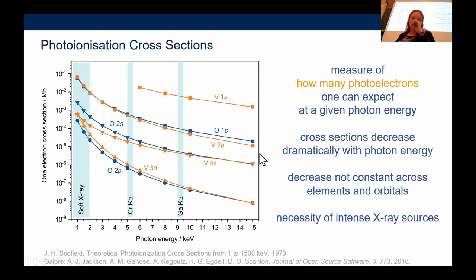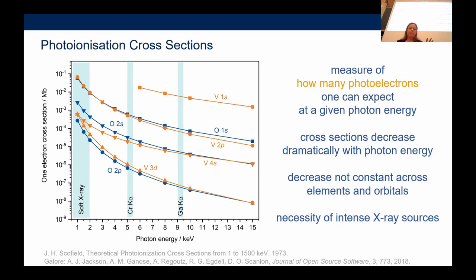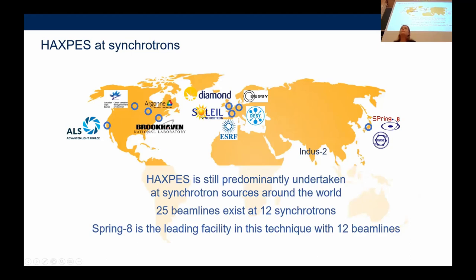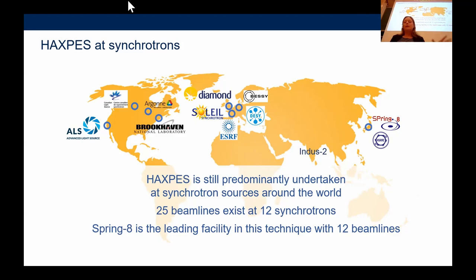So why don't we all have a HAXPES machine in the lab? The biggest challenge when moving from soft to hard X-rays is the dramatic drop in photoionization cross-section — basically how many photoelectrons you get for a specific atom and orbital. The y-axis on the cross-section plot is logarithmic: moving from the soft X-ray range to hard X-rays, it drops by orders of magnitude. Your signal for the same orbital from the same atom will be three, four, or five orders of magnitude lower. This is why you need very intense X-ray sources, and for a long time the only place to get those was at a synchrotron.